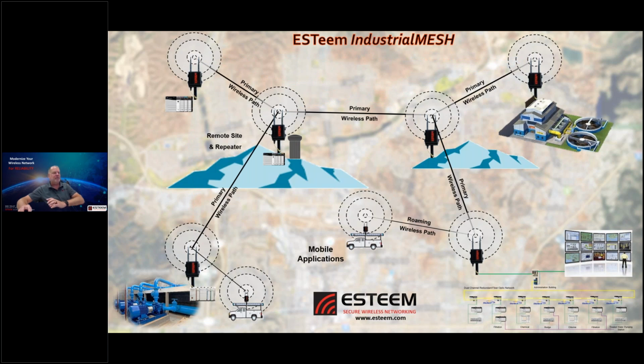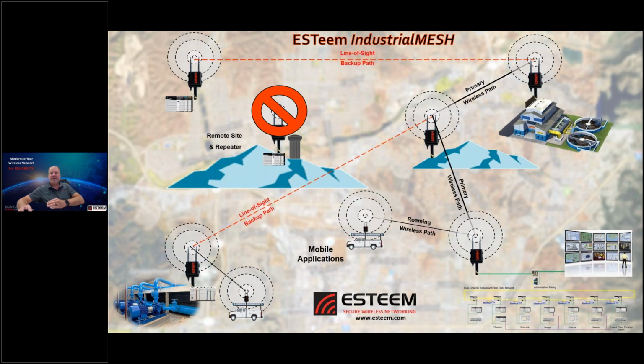Everybody's happy, everybody's communicating, and we may have some instance, say the tank is going to be getting painted, so the maintenance workers unplug that. Now we lose this one. What's going to happen is it reroutes itself based upon the information you configured for your path costing or path length. We're going to move over here.